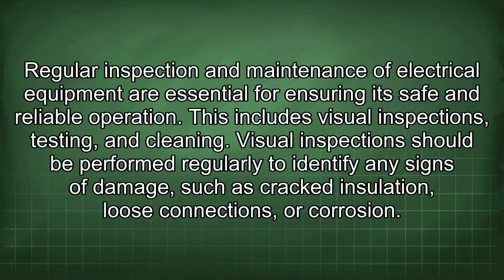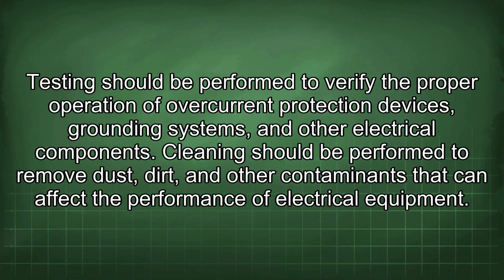Regular inspection and maintenance of electrical equipment are essential for ensuring its safe and reliable operation. This includes visual inspections, testing, and cleaning. Visual inspections should be performed regularly to identify any signs of damage, such as cracked insulation, loose connections, or corrosion. Testing should be performed to verify the proper operation of overcurrent protection devices, grounding systems, and other electrical components. Cleaning should be performed to remove dust, dirt, and other contaminants that can affect the performance of electrical equipment.